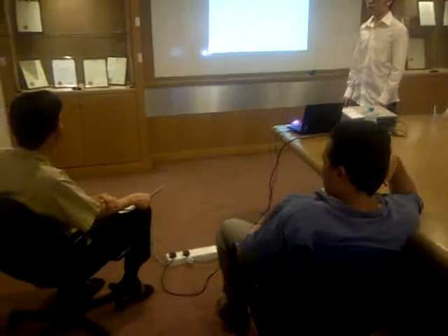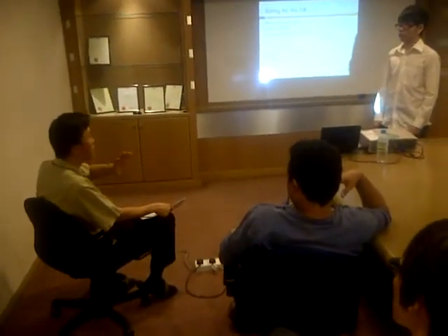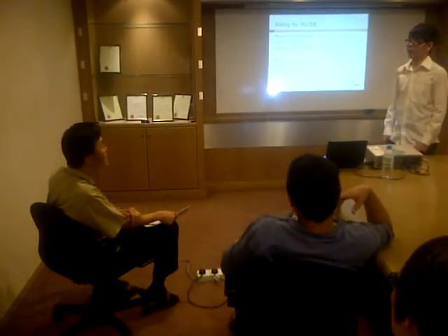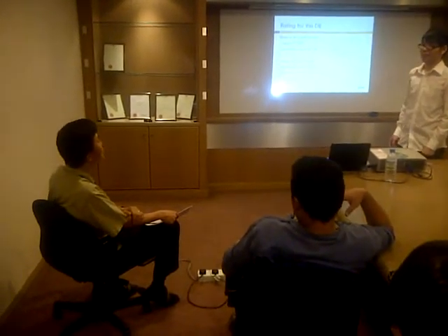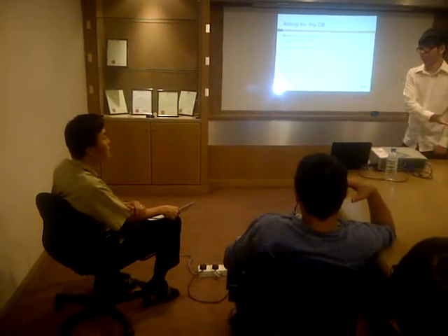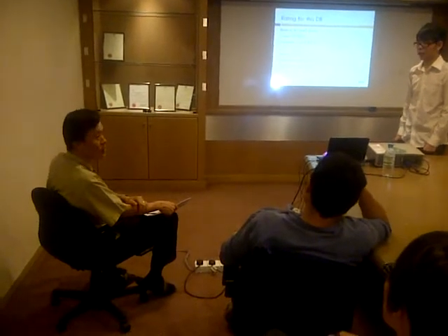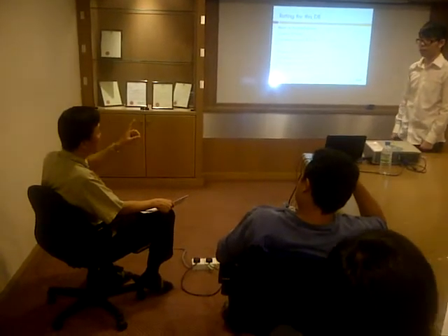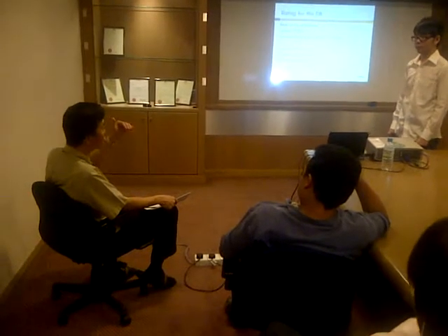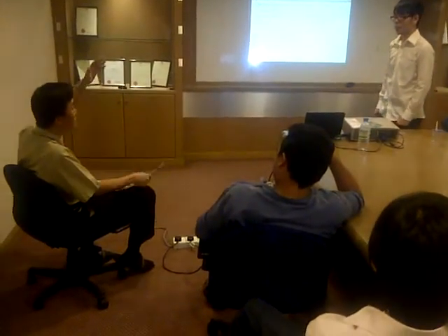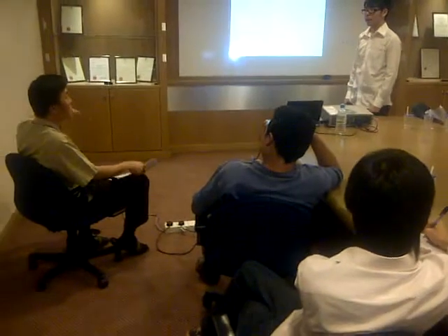But by looking at the library, did you conduct any survey at peak time? How many people are utilizing the socket outlets? We can't, because we don't have the time. Because during their class, we also have class. Okay. I will recommend you do it, because a lot of the time when we do design and we're not sure, we normally go to the actual place to study how they operate. From there we can know what we call the load profile.